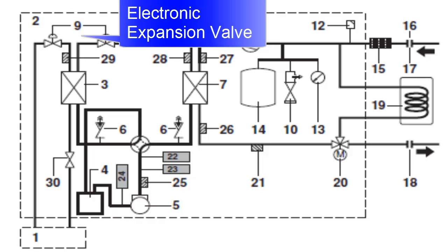Check the wiring connections, sensors, and where they're hanging out. Double-check the wiring connections for that electronic expansion valve.